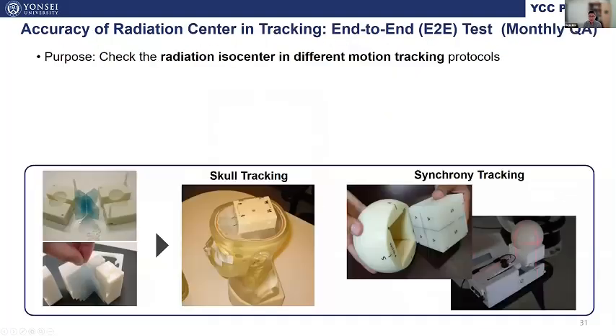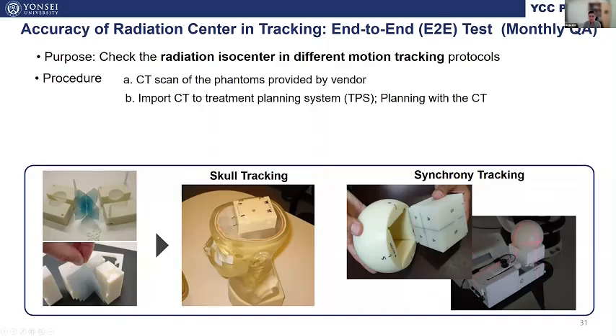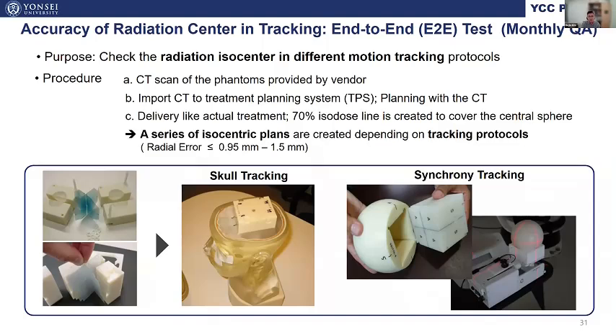We can make it more realistic by the E2E end-to-end test. This is designed to simulate the actual treatment scheme with different types of phantoms or various motion tracking scenarios, as shown here. These phantoms are scanned at the CT simulator, then imported to the TPS, the treatment planning system. The resulting plans are delivered in the treatment console like actual patient treatment. And those distributions are evaluated using film dosimetry.